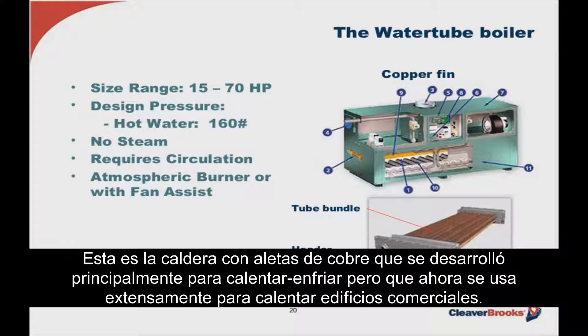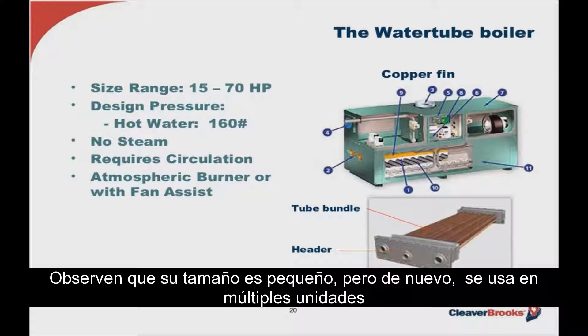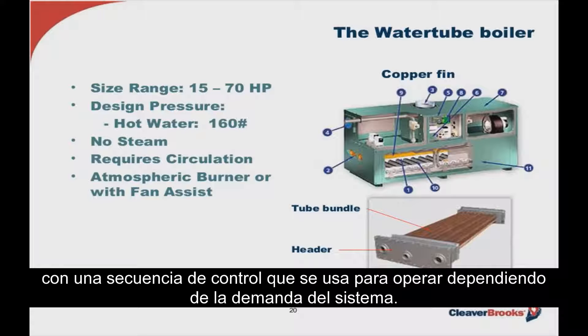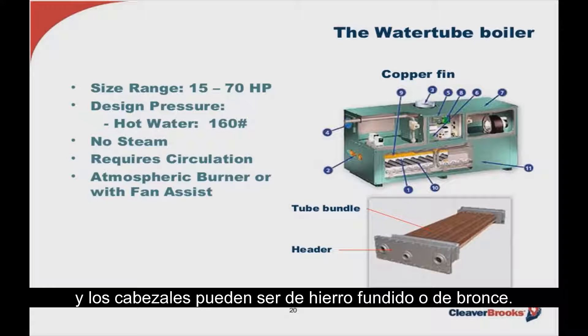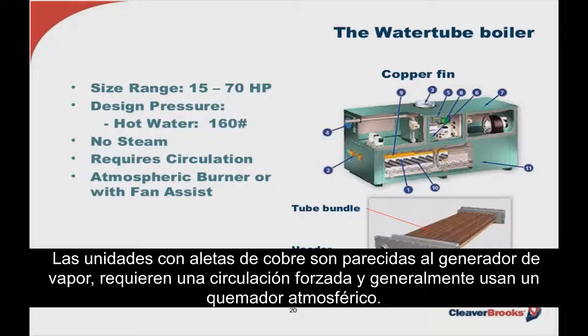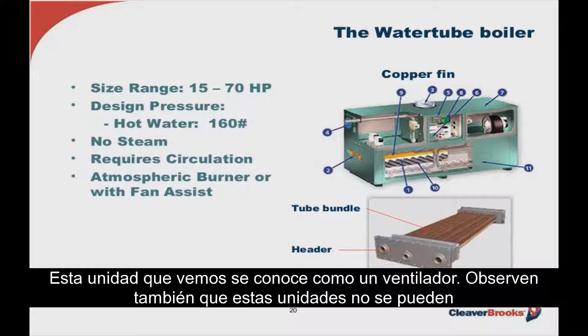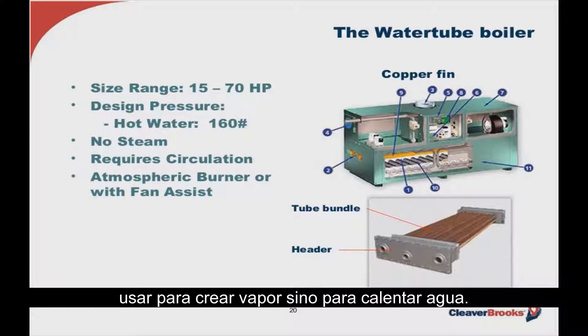The copper fin boiler evolved primarily for pool heating but is now used quite extensively for commercial building heat. The size range is small, and these are normally applied as multiple units with a control sequencer used to stage the firing based on system demand. The tube bundle is normally copper, but cupronickel is also available if water conditions dictate. The headers can be either cast iron or bronze for the same reason. The copper fin units require forced circulation and normally employ an atmospheric gas-fired or fan-assisted burner. These units cannot be used for steam — only hot water heating.